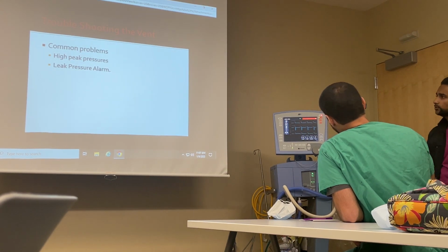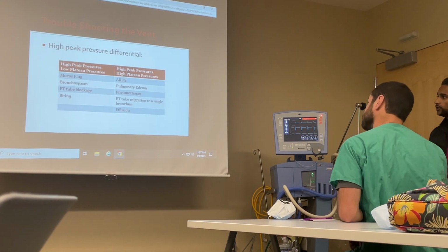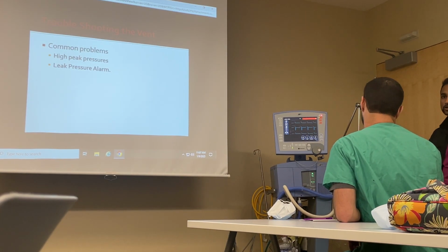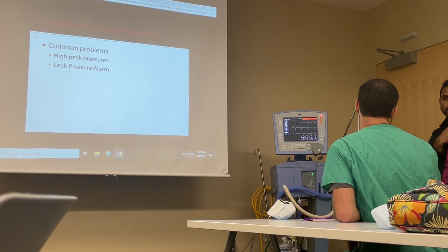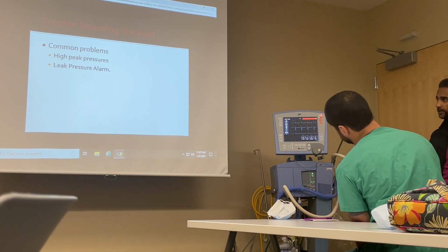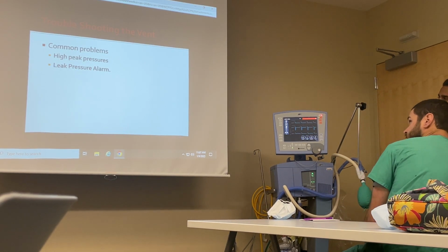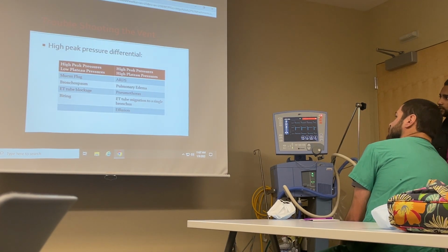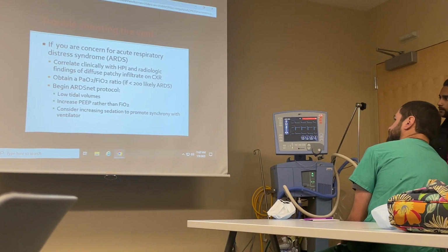All right, let's move on to low tidal volume. That means either there's a leak in the patient's cuff, and you're going to hear a gurgly noise coming in, or it could be just a leak in the tubing, or it's probably disconnected, so just look for that, okay? All right. Anything else? You can skip that, it's pretty self-explanatory.